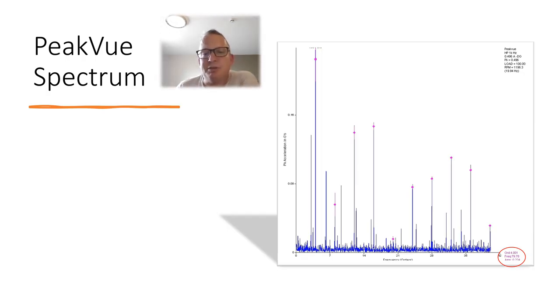So this is a spectrum we had on site, this is your PeakVue spectrum. The values are low, and we can see we've got our harmonic family here. All good thing about the software is you tap the X key and find harmonic families for you straight away. So once you've validated your data, confirmed your RPM, couple of clicks on the keyboard and you're deep in analysis.